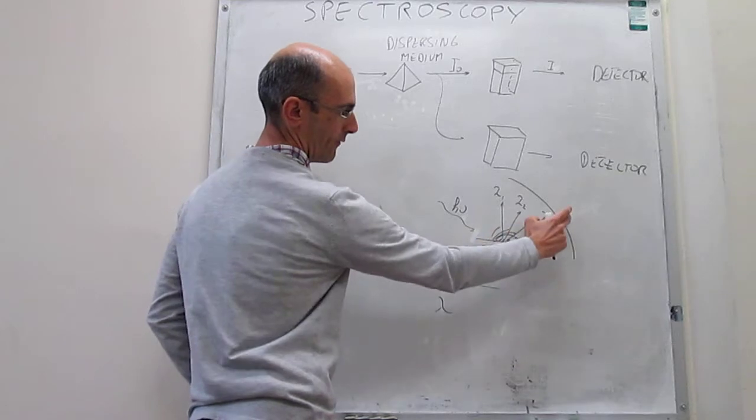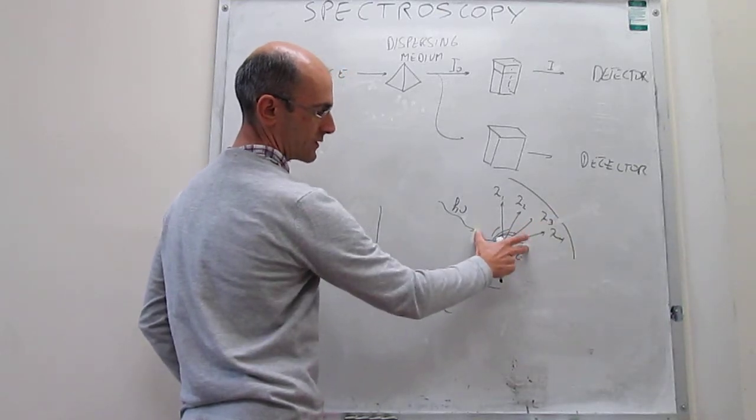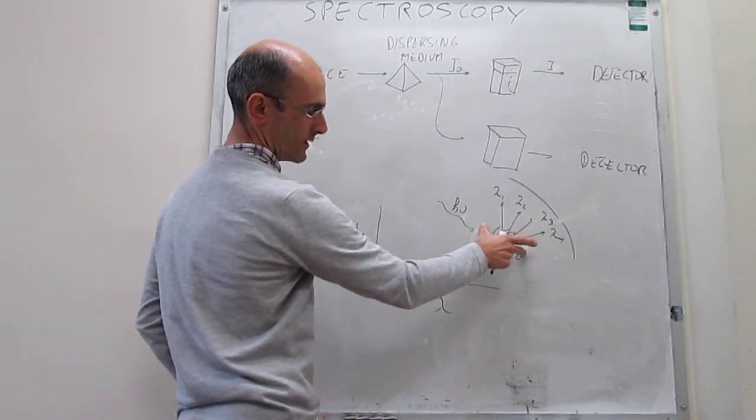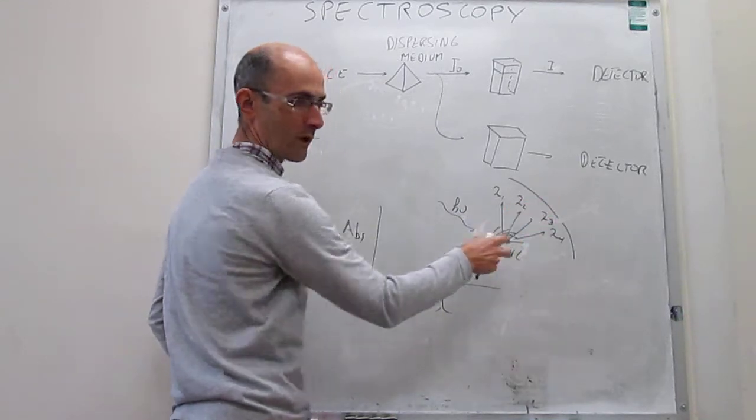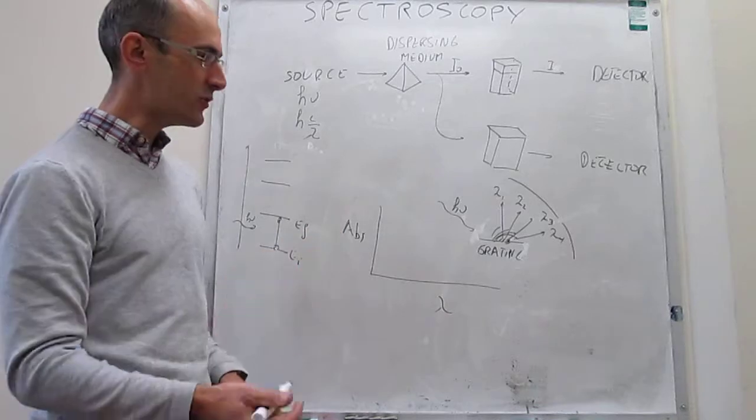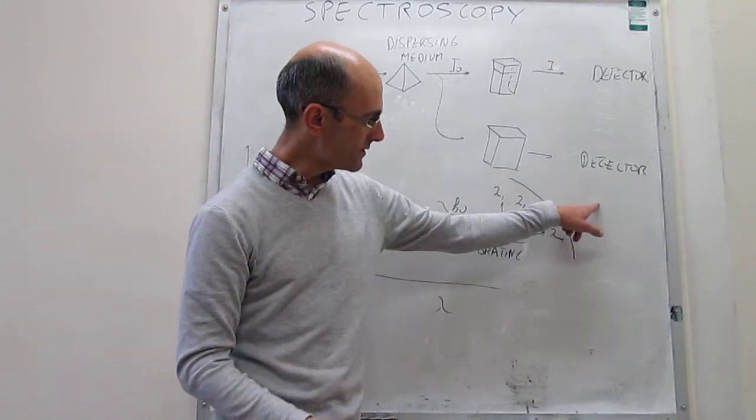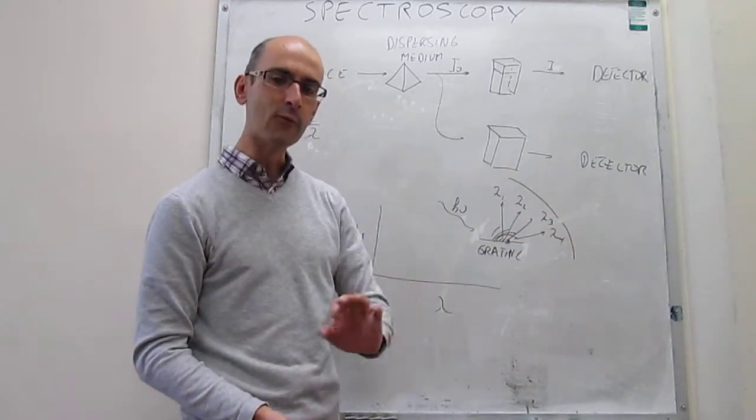First you have λ₄ coming out. If you rotate it this way, then λ₃ will come out. Rotate it a little bit more, then λ₂ will come out. Rotate it more, λ₁ will come out. And through that rotation, you can send radiation in this direction of a specific wavelength.